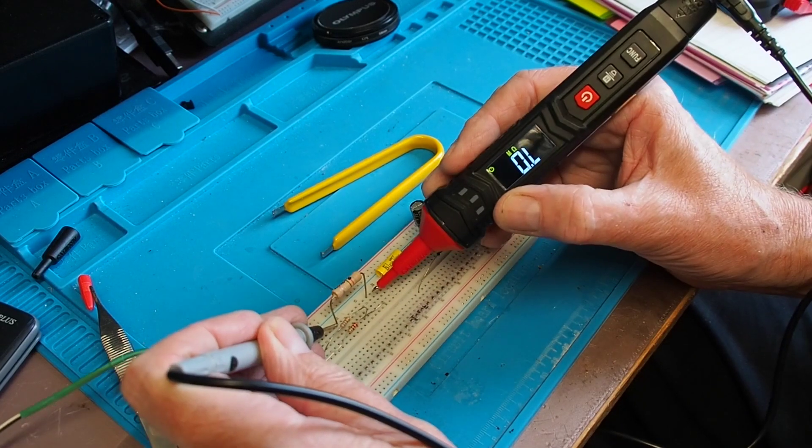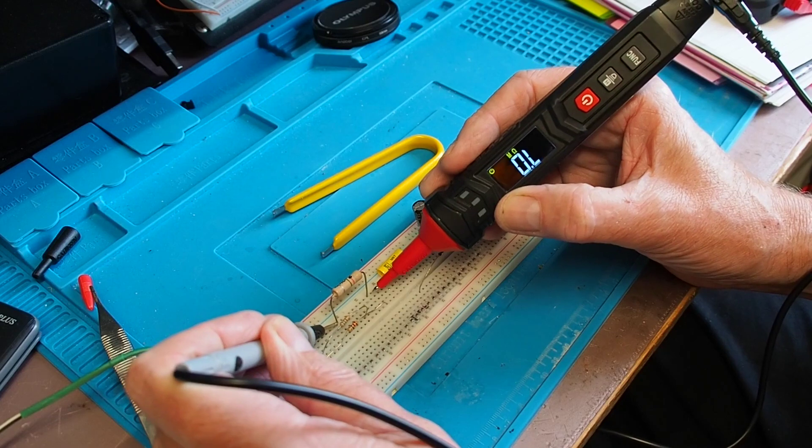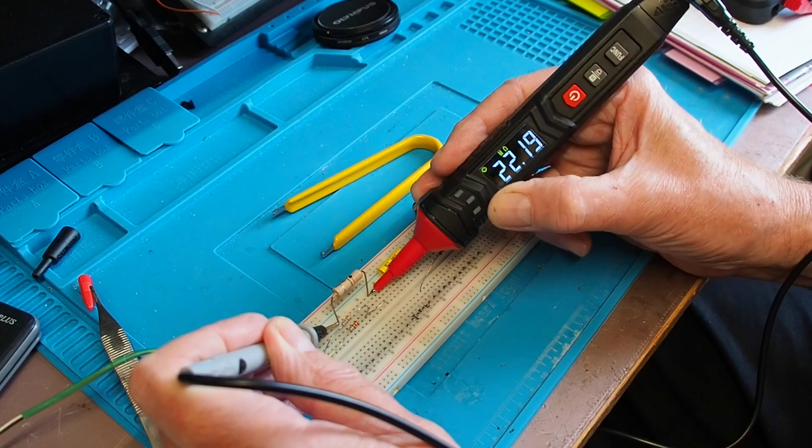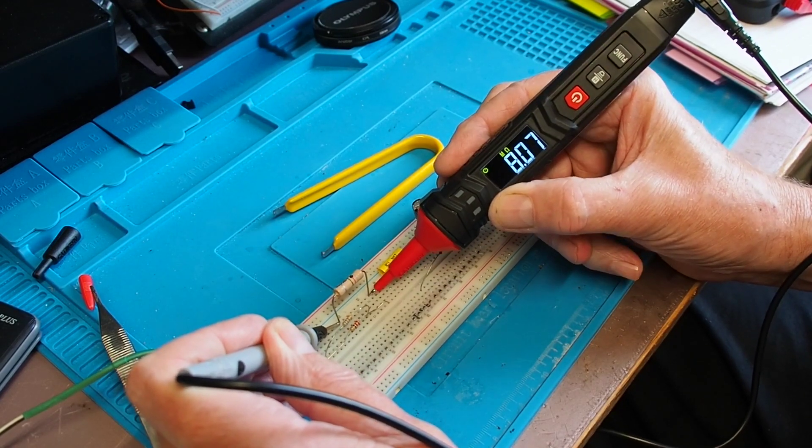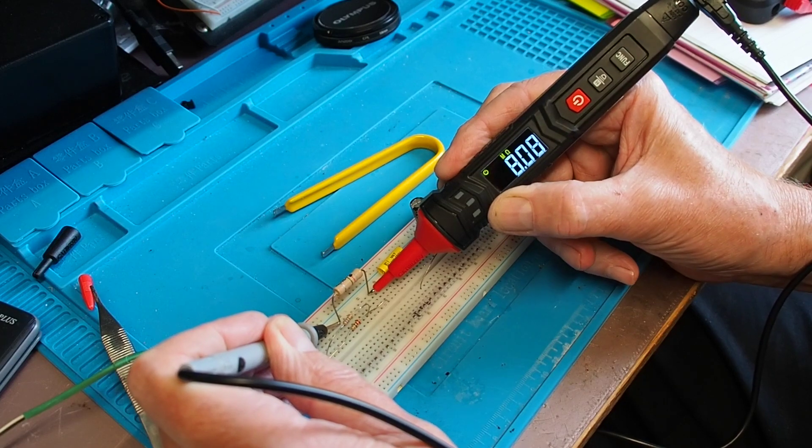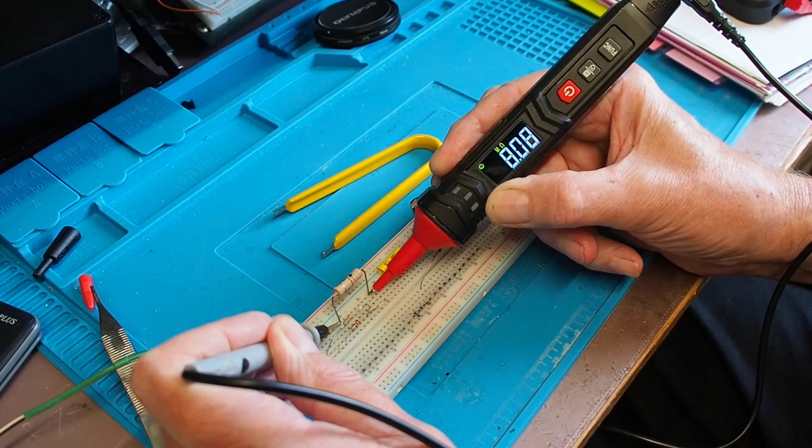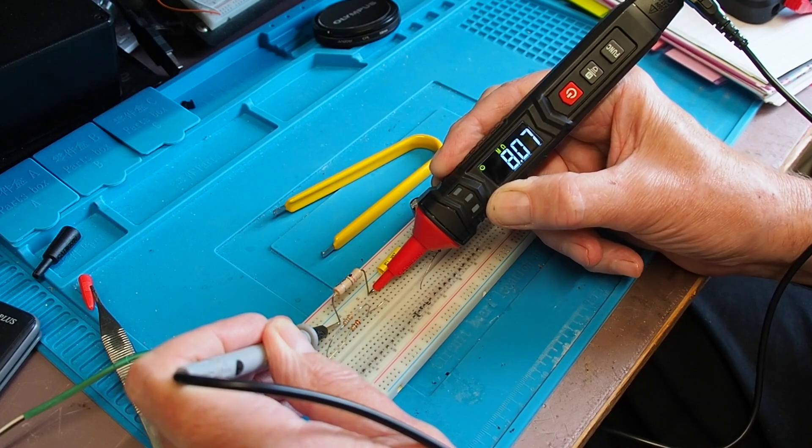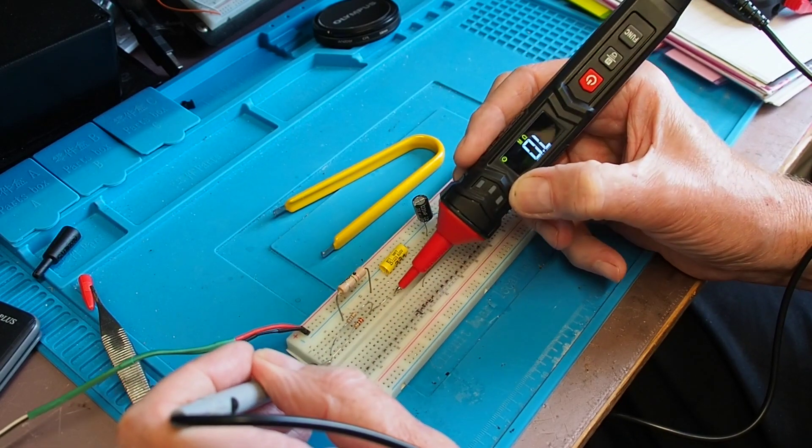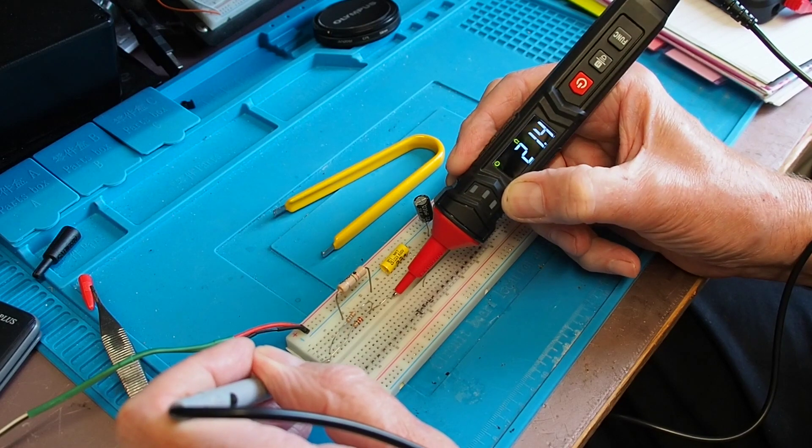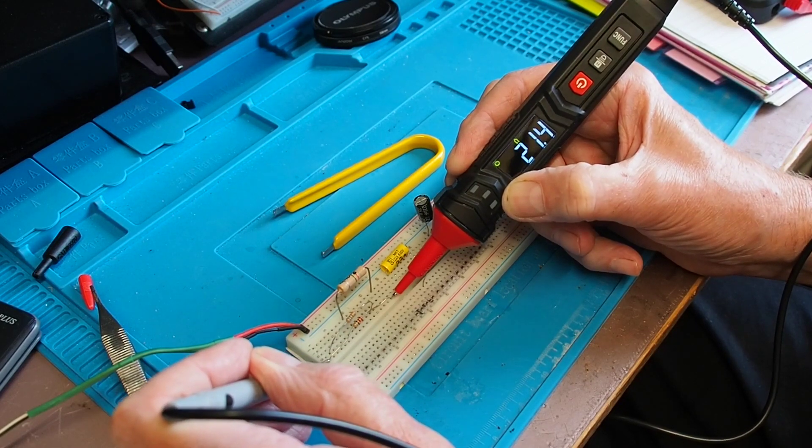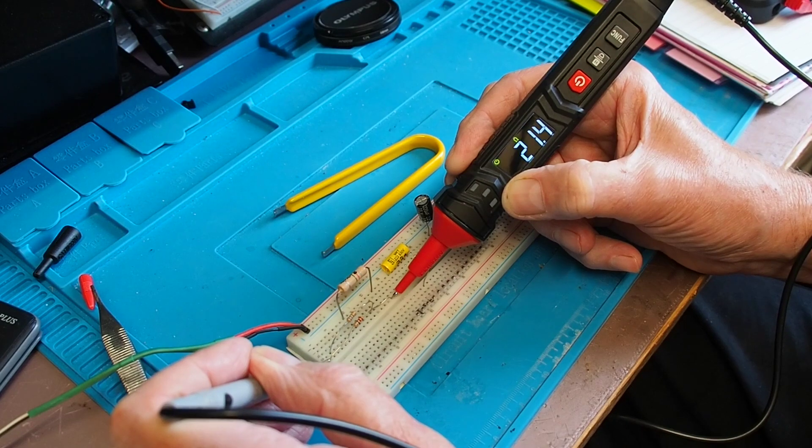So I'm going to start with the resistance. I've got it in resistance mode. So you may recall, or maybe you don't, but it's supposed to go up to 40 megaohm. I haven't got anything like that. What I've got here is about 8.05 megaohm. That's making it 8.08 megaohm, so well within the tolerance.